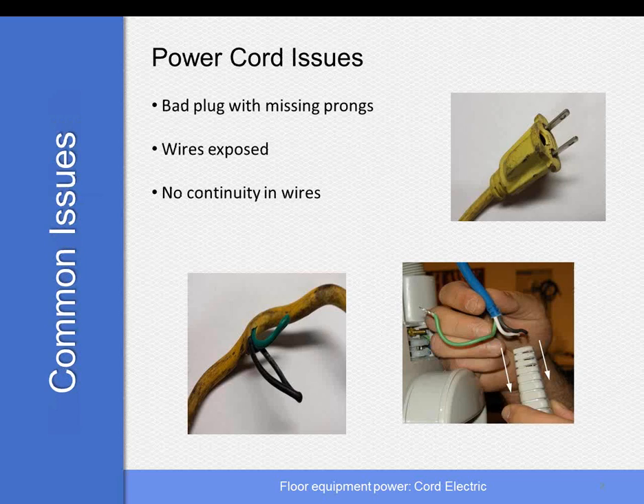First thing you run into is a power cord issue. Usually it'll be a bad plug with missing prongs. They get kinked and the wires get exposed. Usually what happens with the kinks, the wires will break, you won't see it, so there will be no continuity in the cord.